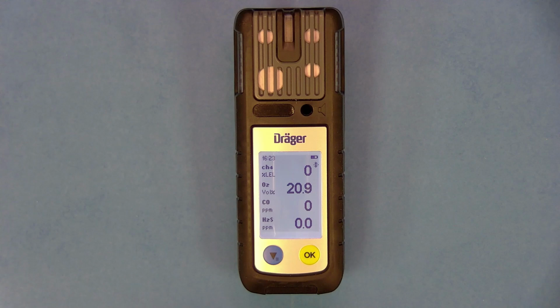You will typically zero your monitor if you are seeing low readings, whether they're positive or negative. When you zero your monitor, you are telling your sensors that you are in 20.9% oxygen, in a location that contains no hazards or explosive gases. Therefore, make sure you only zero your monitor in an area that you are confident has no hazardous gases in it.